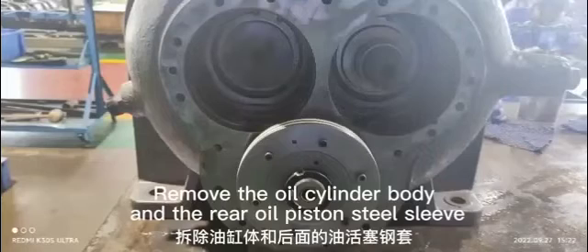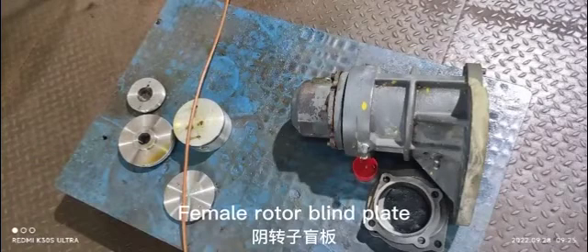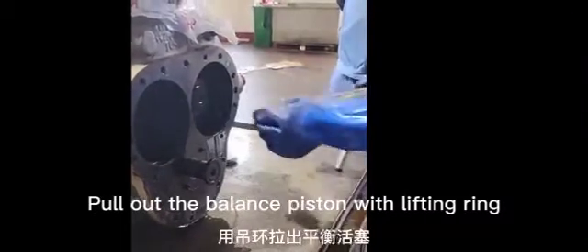Remove the oil cylinder body and the rear oil piston steel sleeve. Release the nut on the female rotor blind plate. Pull out the balance piston with a lifting ring.